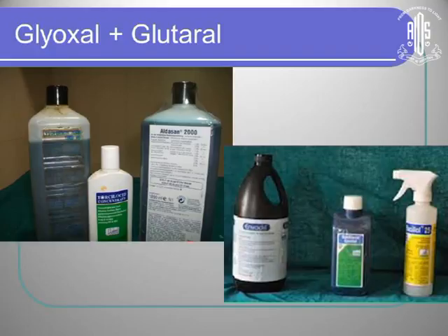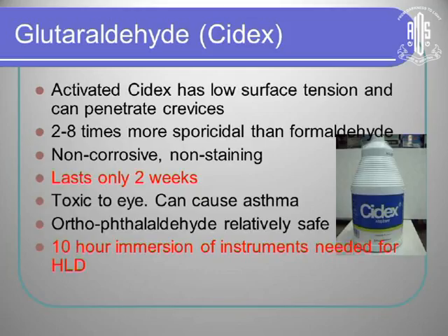Aldehyde-based compounds — but not formalin — such as glyoxal and glutaral combinations are available in the market. Glutaraldehyde is not nowadays used in ophthalmic setups. Some hospitals use glutaraldehyde for disinfecting sharp instruments, but it is not advisable, because for proper high-level disinfection you have to keep instruments immersed for 10 hours. There is no point keeping them for only 20 minutes and then using them for surgery.